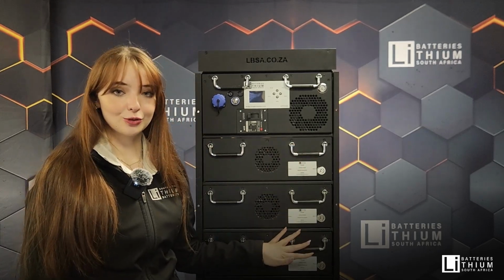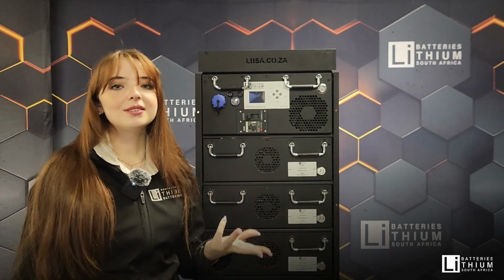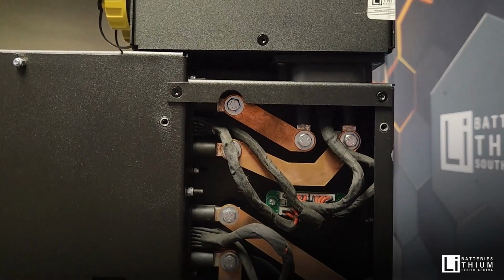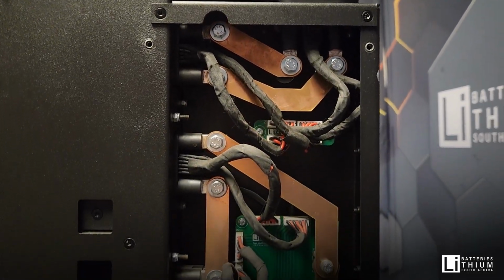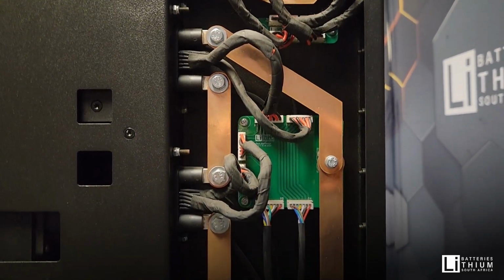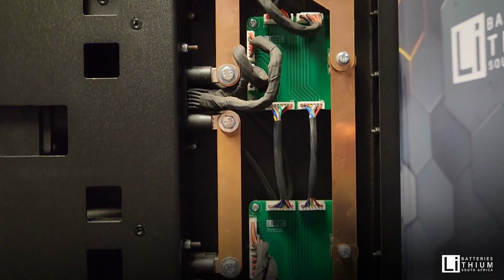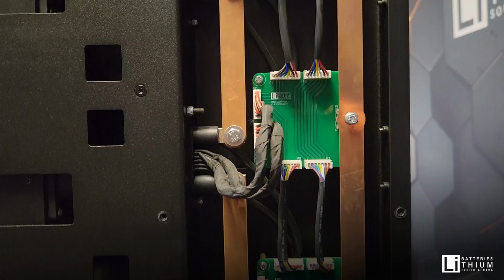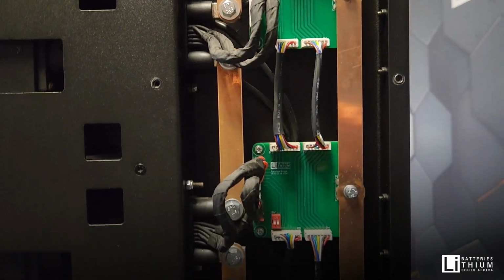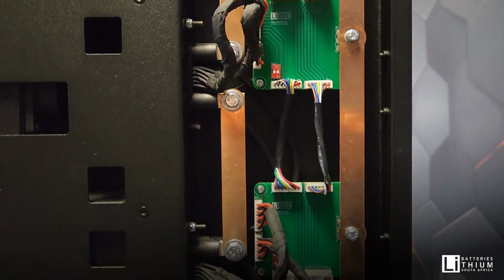Now, as you can see, there are no wires connecting the modules to each other. We have designed the battery to be completely wire-free where that is regarding. At the back of the rack, there are bus bars that connect each module in series. And then there's also a communication board that communicates to the controller for every cell's voltage and temperature.